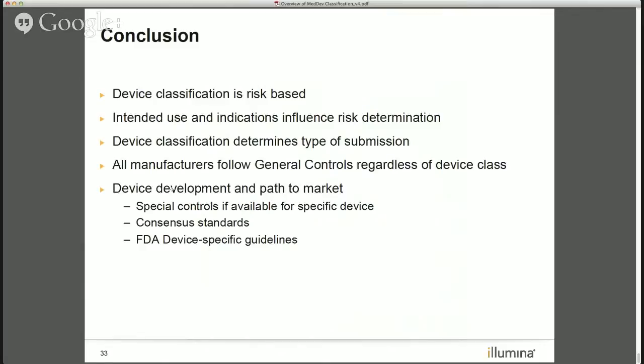In conclusion: device classification is risk-based. Intended use and indications — the words you choose — can definitely influence the risk determination. Device class determines the submission type: exempt, 510K, or premarket approval application. All devices follow general controls regardless of class. And there are many tools to help you on your development path: special controls for specific device categories, consensus standards, and FDA-specific guidance documents that can be device-specific or generic.